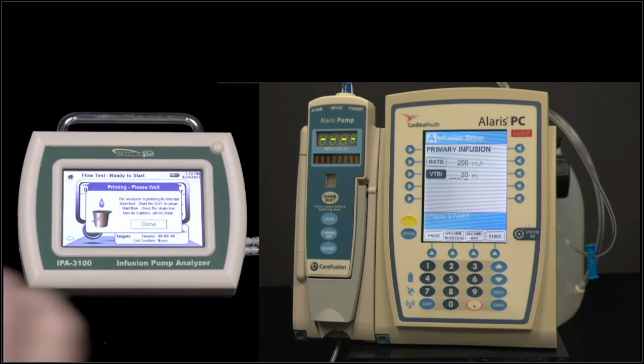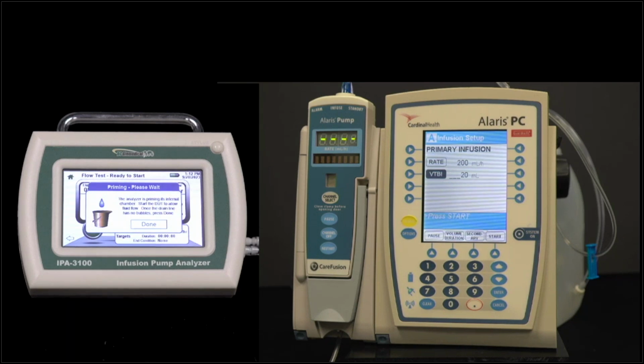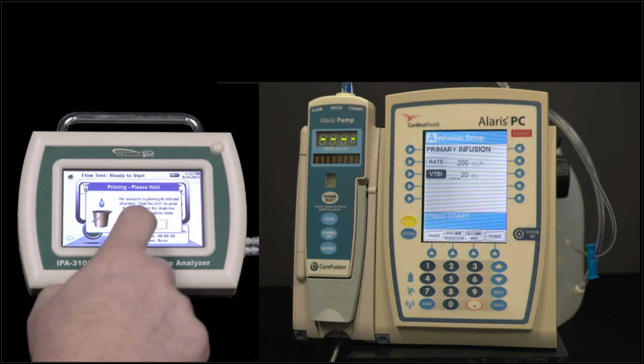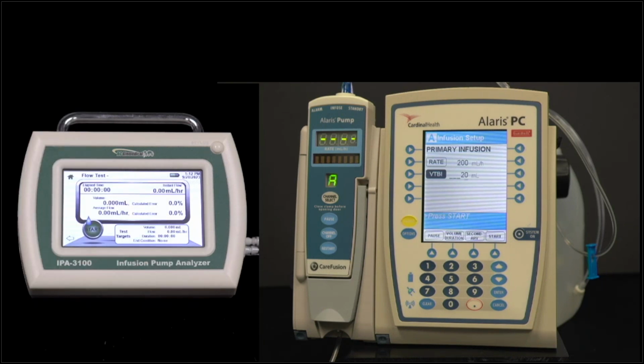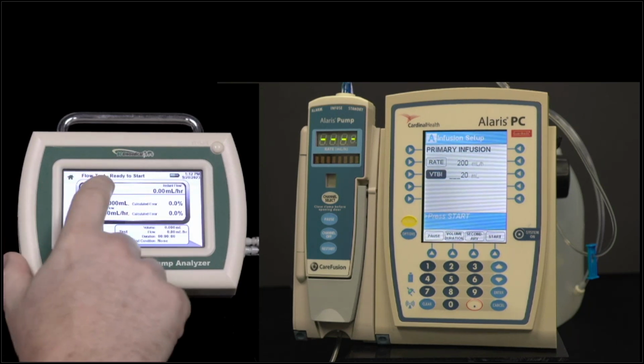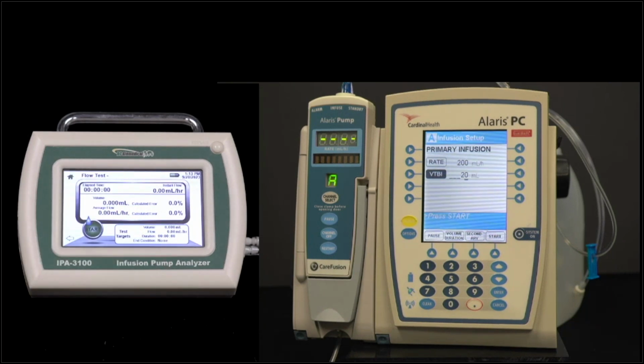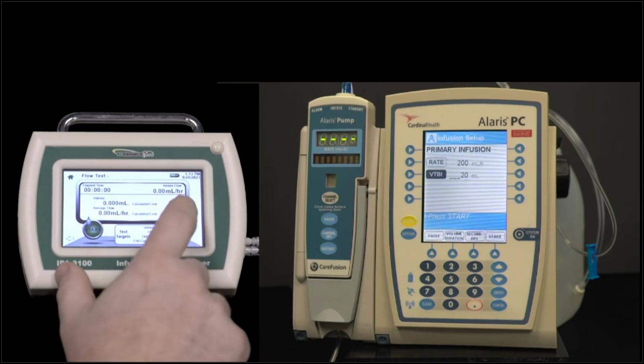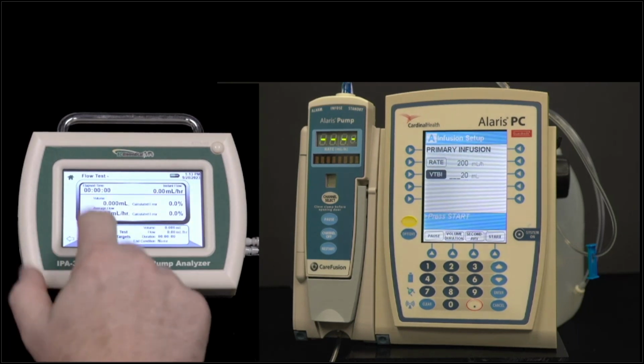Now, remember, I primed the tubing by using the drain mode. So the IPA-3100 thinks that it's been drained, and it's going to say, well, before you can run a test, you need to prime. So I'm going to say, yep, we already primed. Hit that button there, and now it's ready to test. So the test screen at the top, it tells me I'm running a flow test, and it tells me it is ready to start. So I'm going to try and tweak in my focus here a little bit better. So now it's ready to start, and all I have to do is press the start button here.